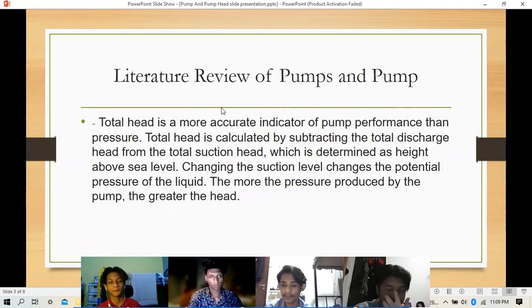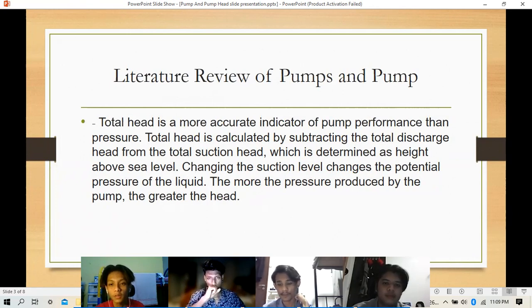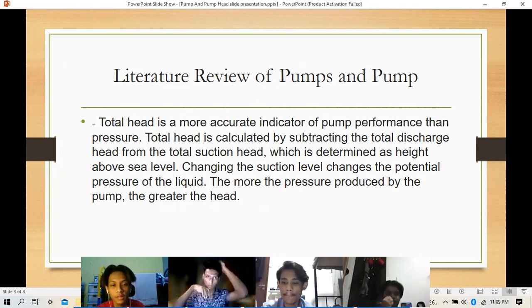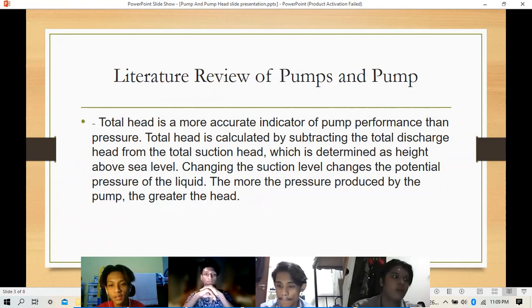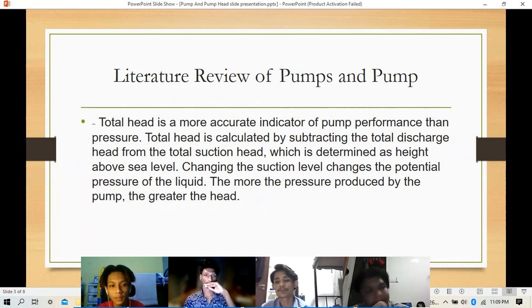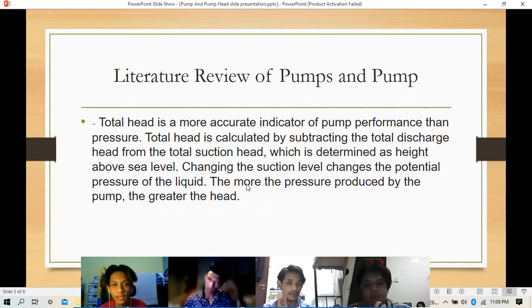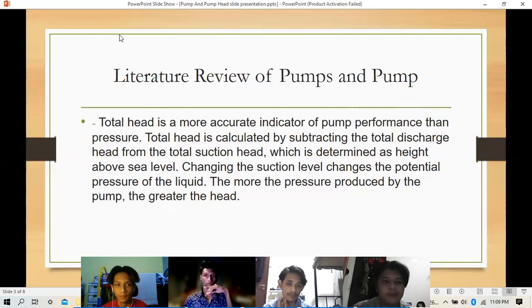Okay, thank you. So now I will present the literature review of pumps and pump head. Total head is a more accurate indicator of pump performance than pressure. Total head is calculated by subtracting the total suction head from the total discharge head, which is determined as height above sea level. Changing the suction level changes the potential pressure of the liquid. The more pressure produced by the pump, the greater the head. Okay, that's all for me. I will pass to Daniel Hamdi for the next slide.